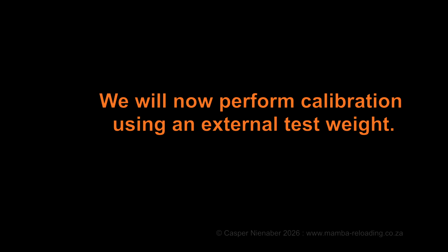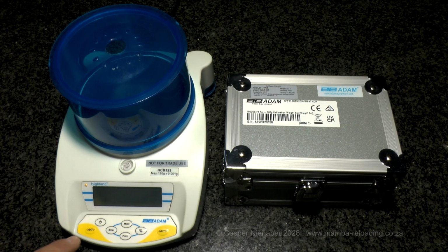We will now perform calibration using an external test weight. To enter the calibration menu, press the On button, then press and hold both the Sample, SMPL, and Print buttons simultaneously until Unload appears. Press the yellow Zero Tare button. The display shows A, 60 grams. With the Mode button, this can be changed to 120 gram test weight. Press the yellow Zero Tare button to confirm calibration with a 60 gram test weight.